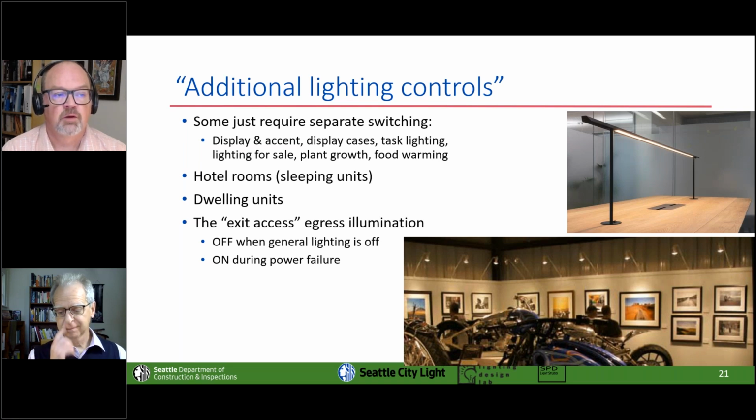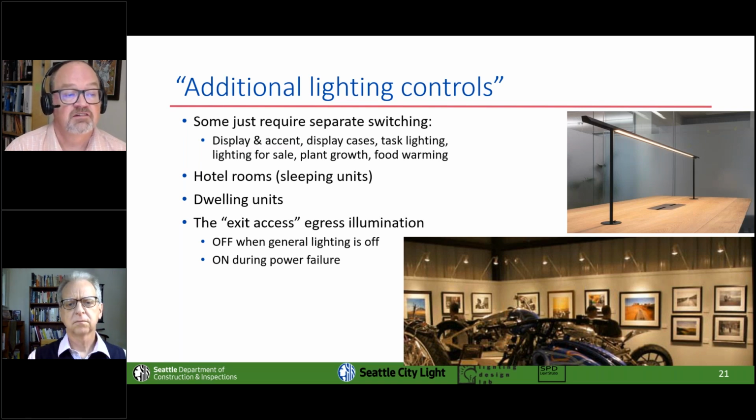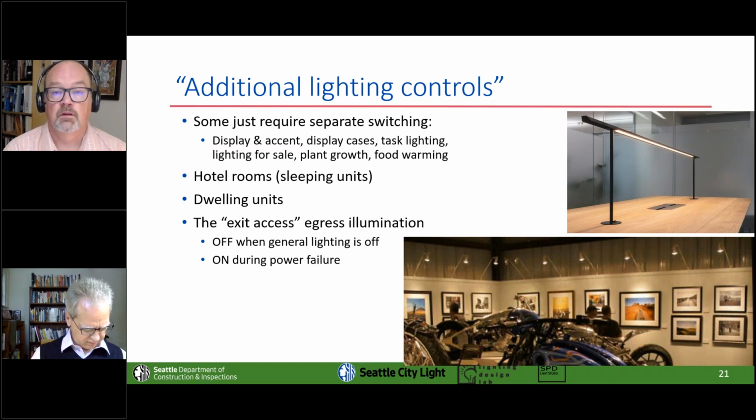Well, and just a quick follow-on. Jose follows on: in California, we typically do not provide occupancy sensors in electrical rooms, for example. Is this a safety issue? So Jose, what I would tell you is an electrical room is not on that list of required spaces that need occupancy sensors. So take it as written that in places where there are going to be safety issues like that, you're not going to need it in that particular space.